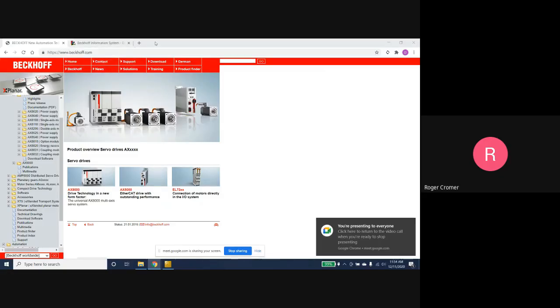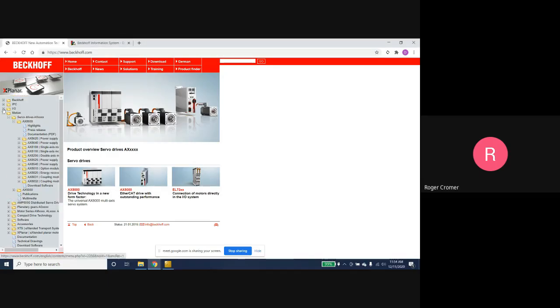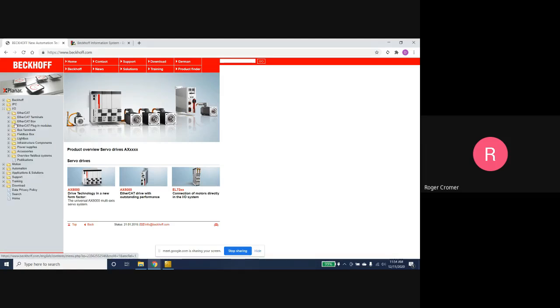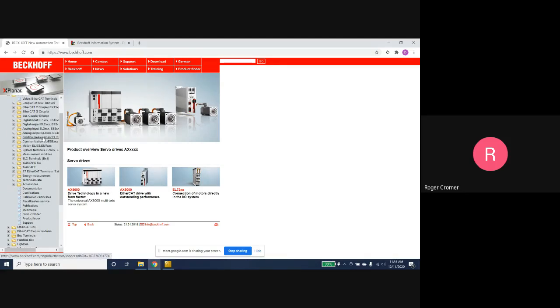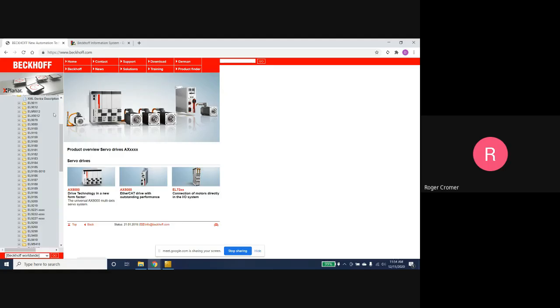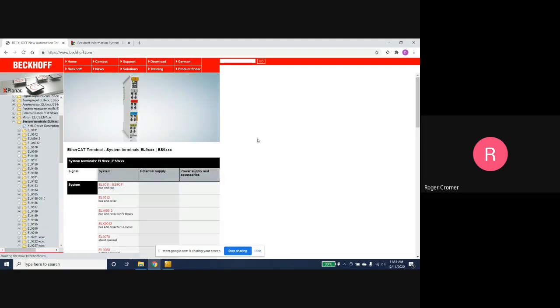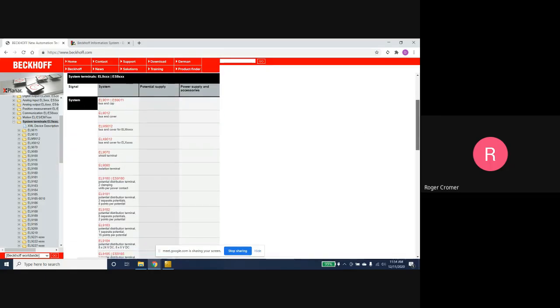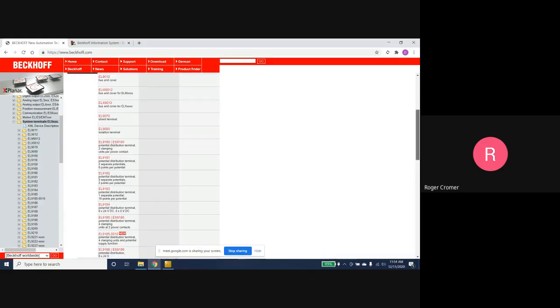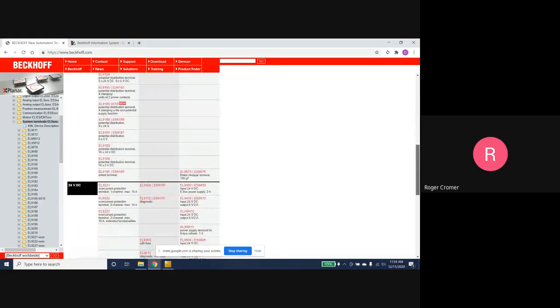Say more, Roger. So you can have passive slices in a system and it won't scan them in. It won't actually see them, but they will still be there. Passive slices are generally ones that begin EL9 something. They don't communicate across the E-bus, but they're there to provide power or something like that into the system. So something we did in Tesla was they had all their safety slices together, and there was a concern that they were going to generate a lot of heat. So we added in passive slices in between the safety slices, and it means that the code doesn't need to be changed at all in the system, and it will continue to work perfectly well.